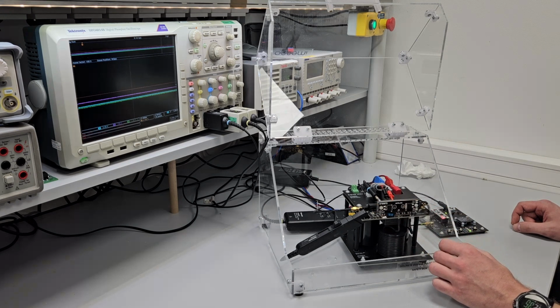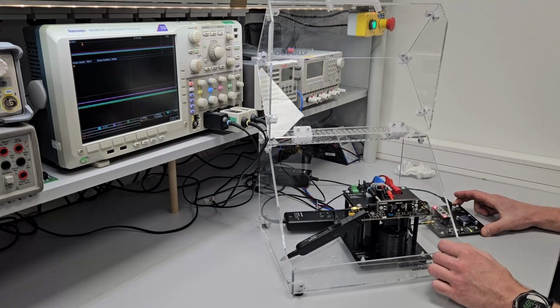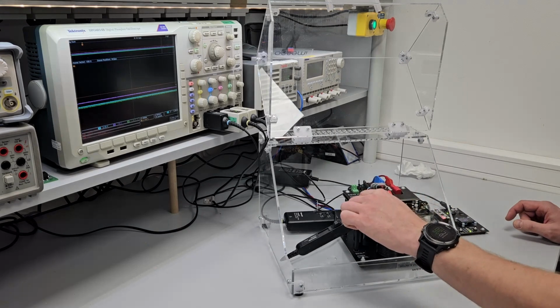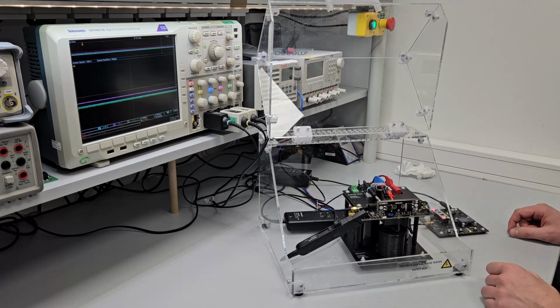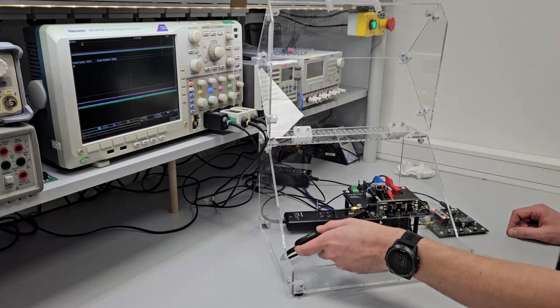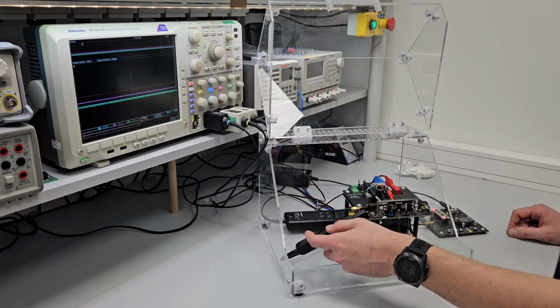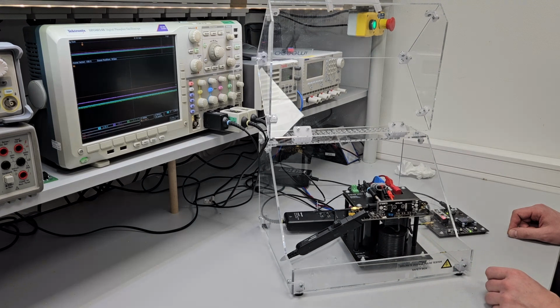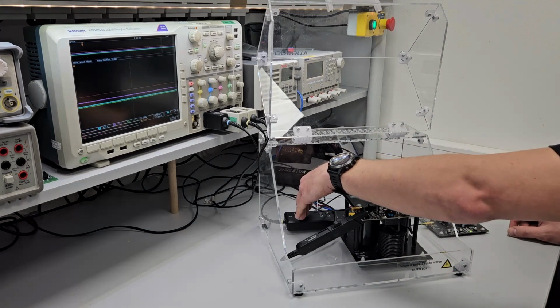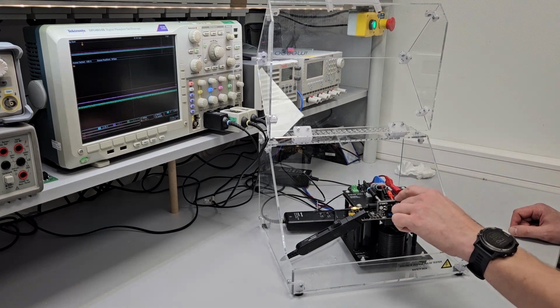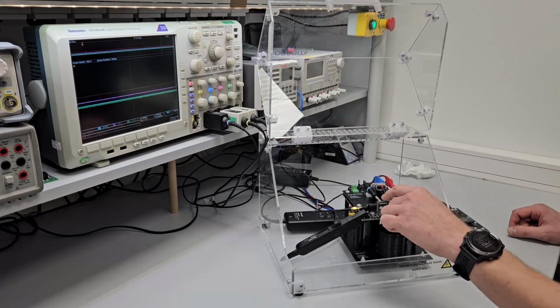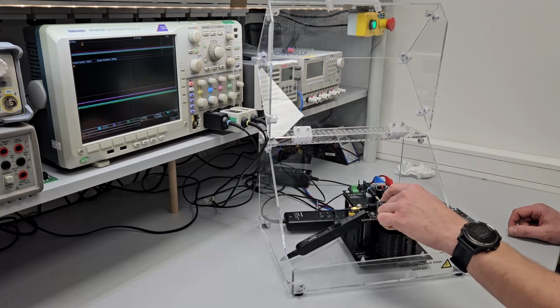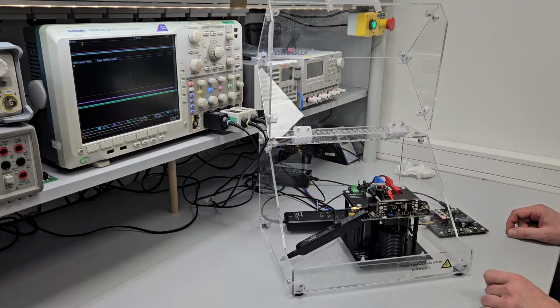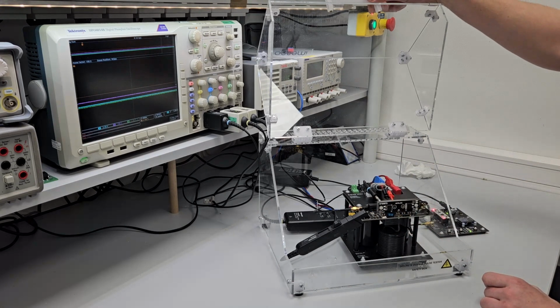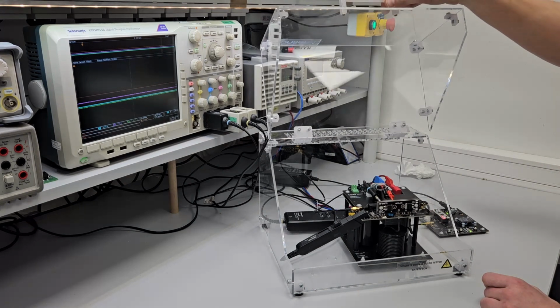For signal generation, I'm using the double pulse generator control board connected through this SMA cable. For oscilloscope sensing, I'm using a current probe attached here on the main board to sense the drain current. For the VDS voltage, I'm using a high voltage differential probe connected directly on the daughter card, and for the VGS voltage I'm using a passive oscilloscope probe also connected directly to the daughter card. Since the system is going to be operated at high voltage, it's always recommended to use a protective safety cover.